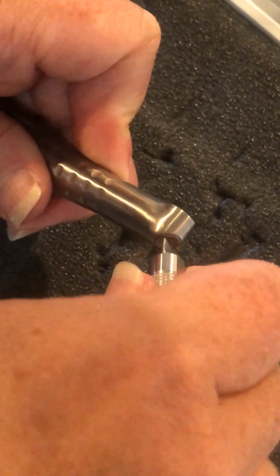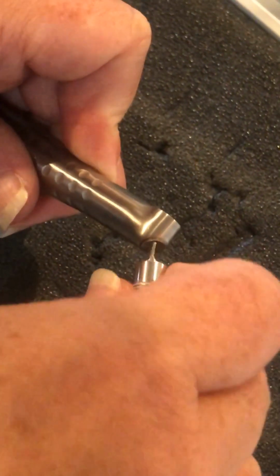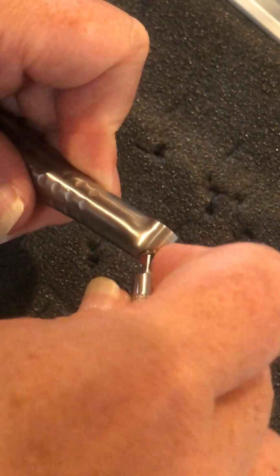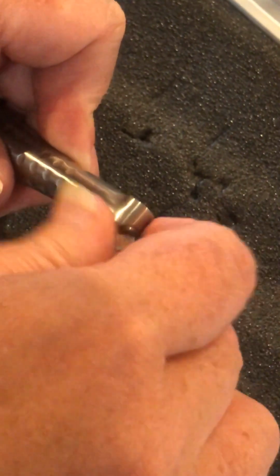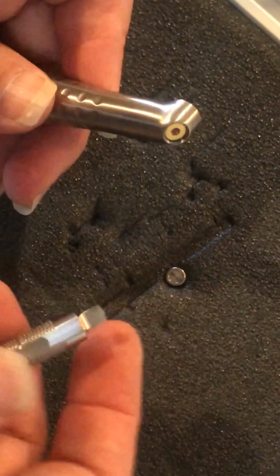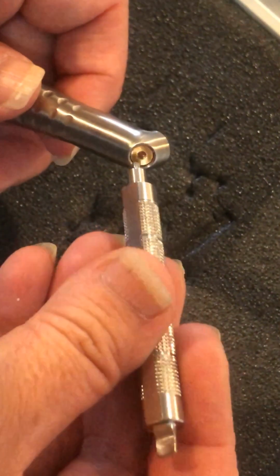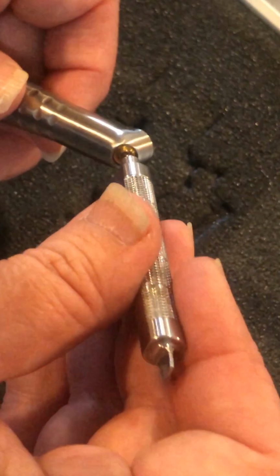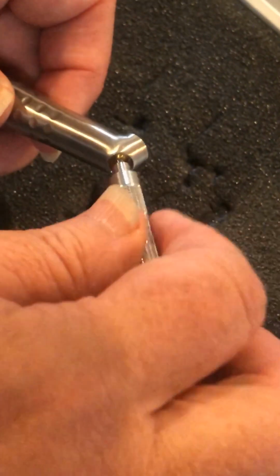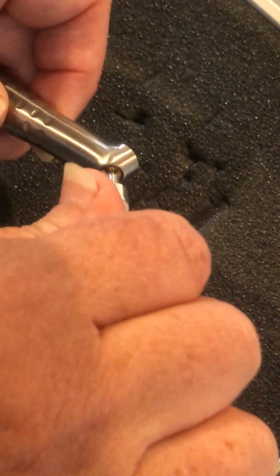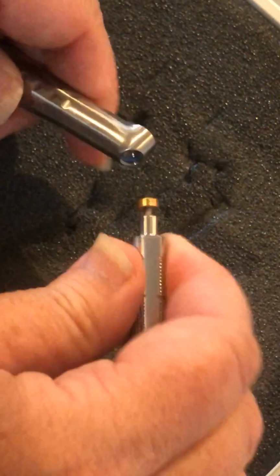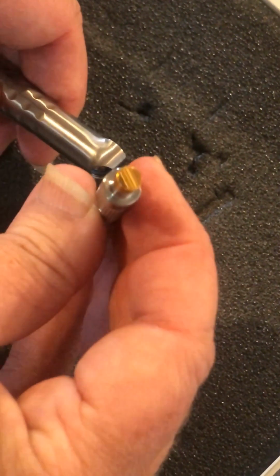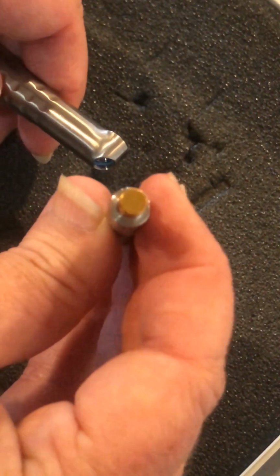And when you put this back in, you only want it to be finger tight, because if you tighten it too tight, especially when you run it through sterilization, it's going to get even tighter, and it's very easy for you to strip that if you do. So now take this male part into here and just turn it to the right so that you thread it. Once you feel it get a good grab, just pull straight out, and that's your mirror. It should always be shiny and gold like that.